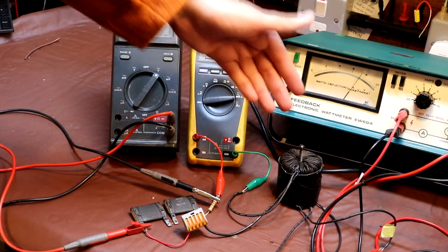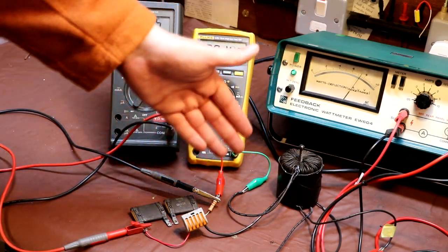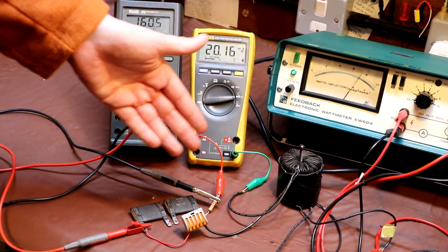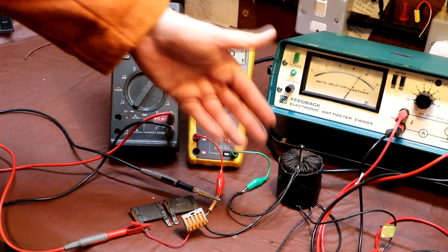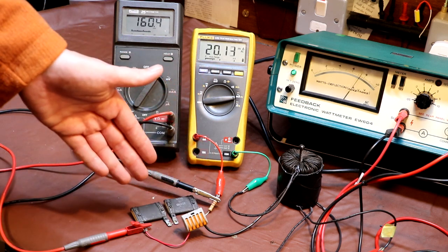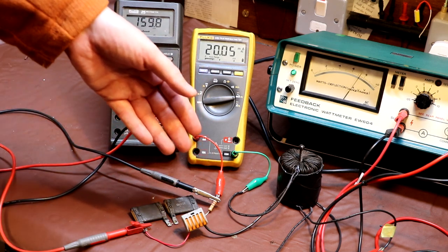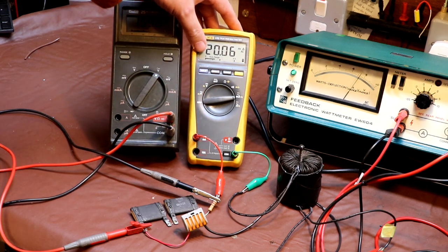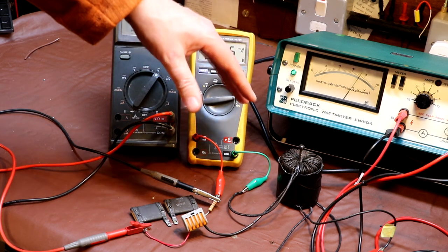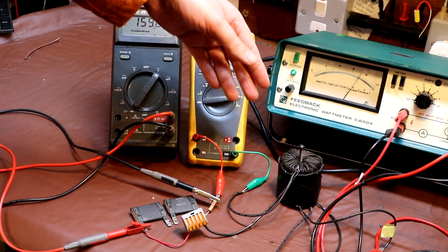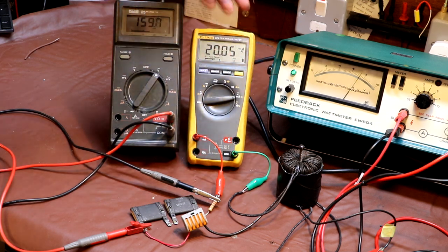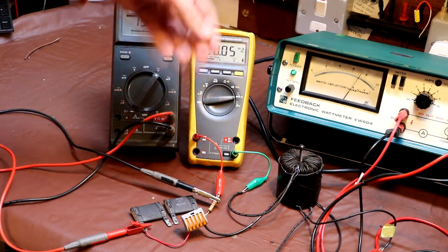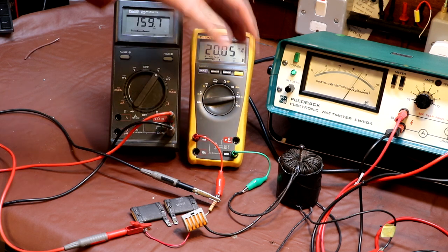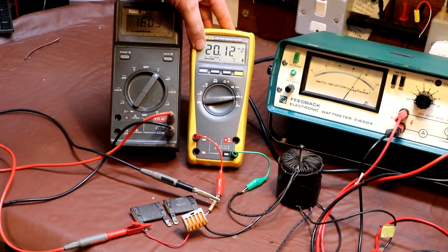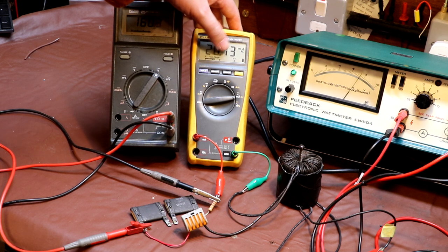Now I've also connected a resistive load to the secondary of our transformer. So the transformer is now actually delivering some useful power, and it's delivering that power into a bank of resistors here. I purposefully arranged this bank of resistors to present a 20 milliamp load to our transformer, because according to the specification sheet that came with this, it says the output current was 20 milliamps. So we arranged those resistors so that we were drawing 20 milliamps of secondary current. We can see that on this meter here. Well, it's just over at the moment, 20.1.